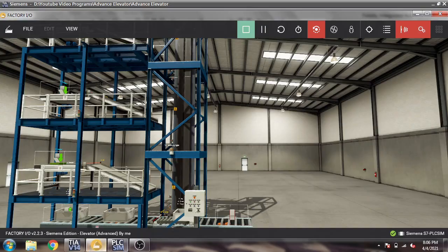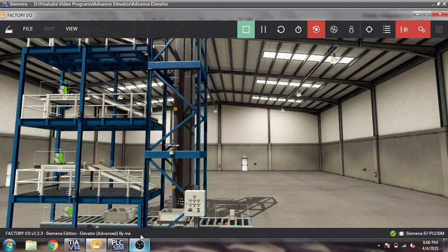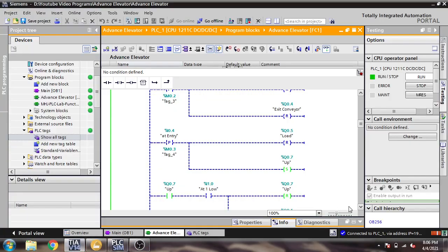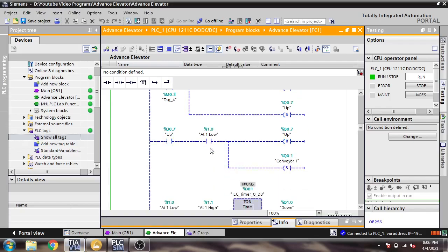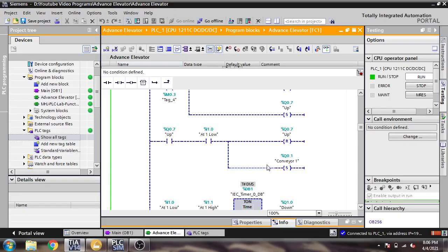After the box passes at-entry, it will reset Load and set Up — meaning it sends the elevator up. You will see it is showing yellow now. Then when it reaches the at-low-1 sensor, it will reset Up.